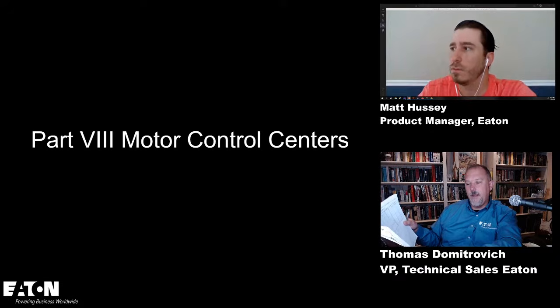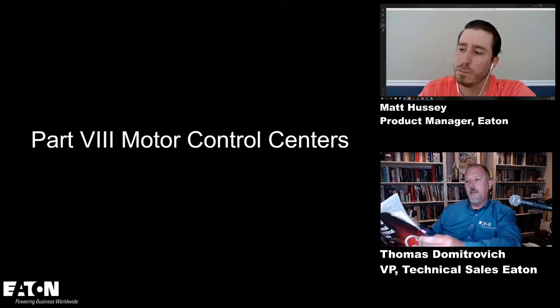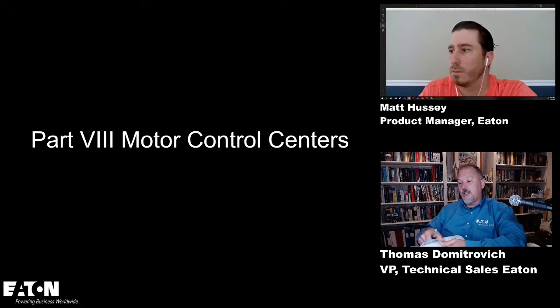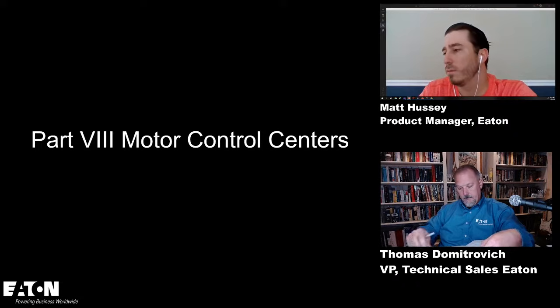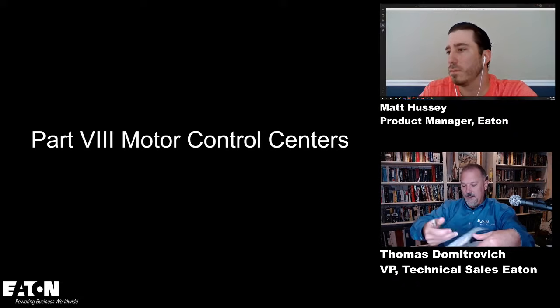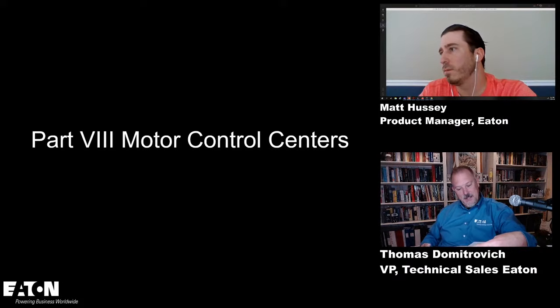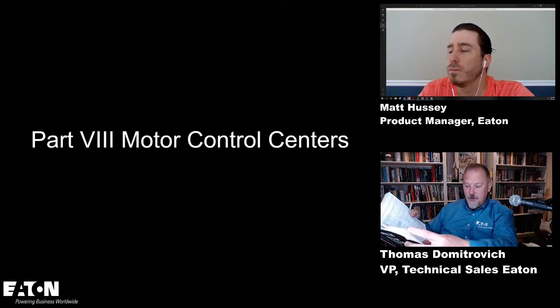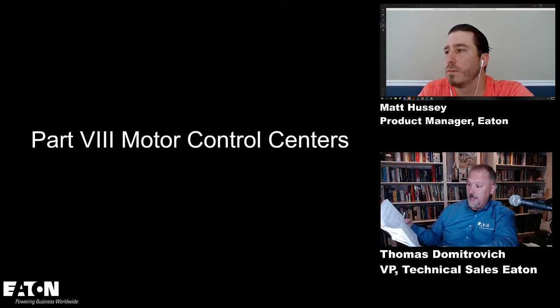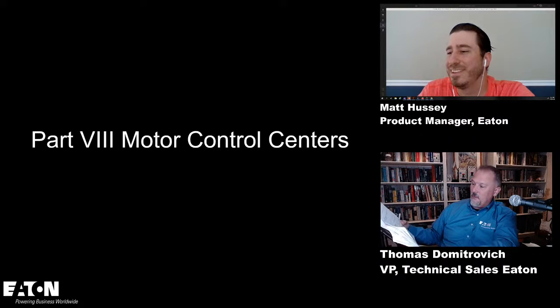Wait a second. Nope, that's the wrong one. That's 13. What does that have to do with motor control centers? Part 7 is motor controllers. There we go. Part 8, motor control centers, is 430.92. This makes more sense. 430.92 through 430.99.